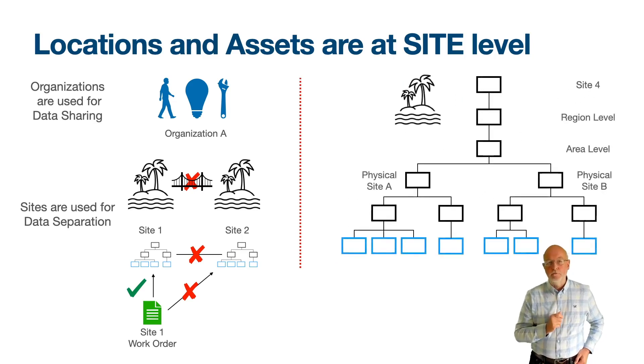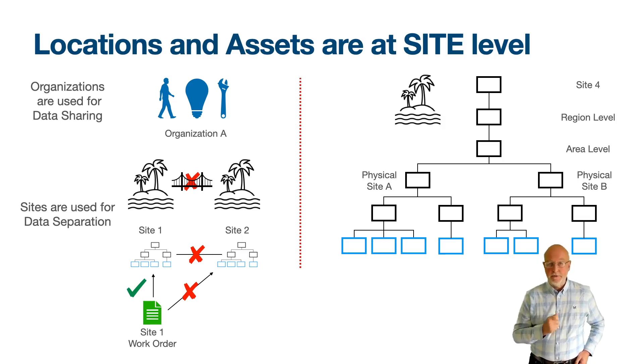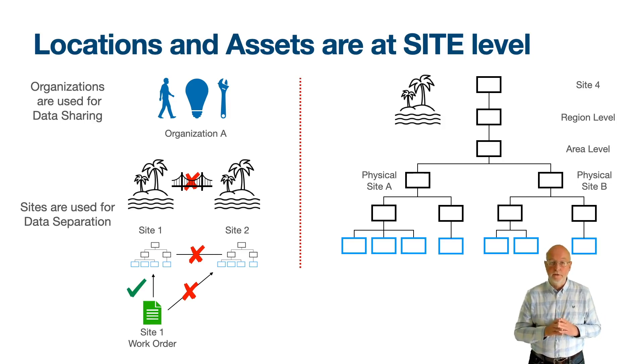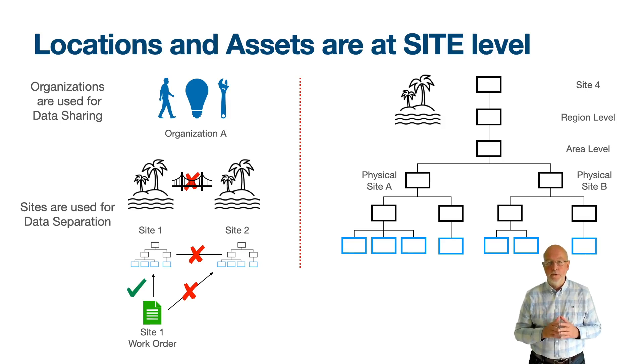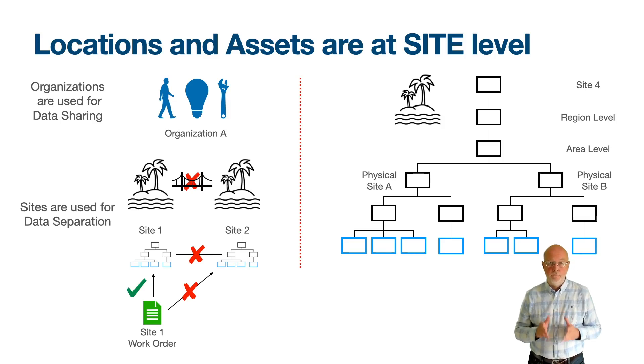You can use a Maximo site to represent multiple physical sites, all sharing the same primary hierarchy. Some organisations with dispersed assets will use the top levels of the primary location hierarchy to describe the regions and areas where physical sites exist. This works well if the regions and areas rarely change, but you need to consider the implications of changing many location records in the hierarchy if region or area boundaries do change. If boundary changes occur frequently, my preference is to use a secondary system.